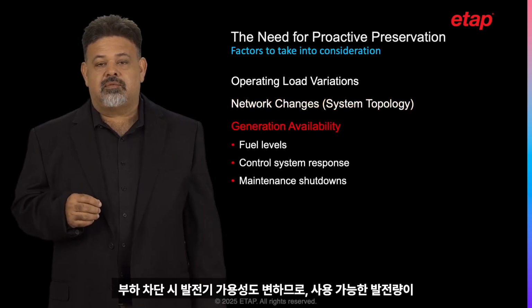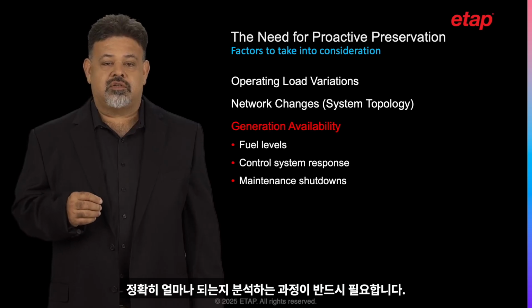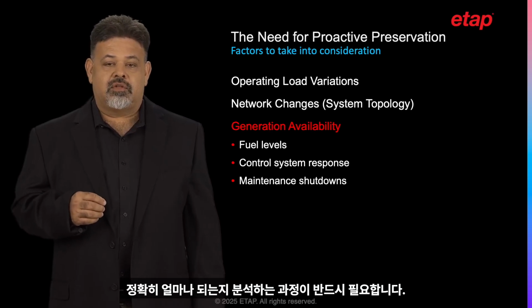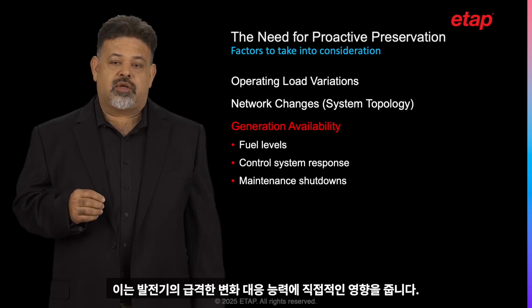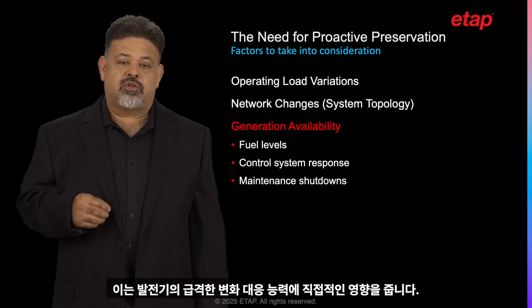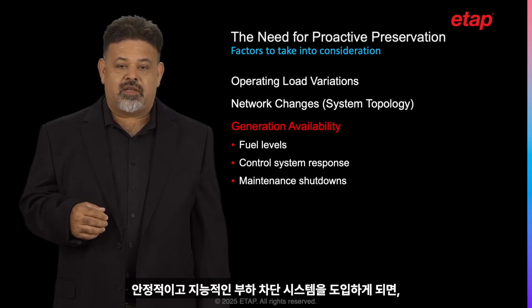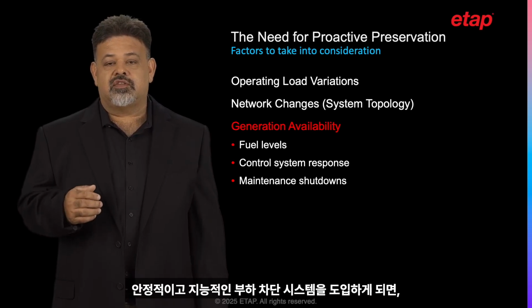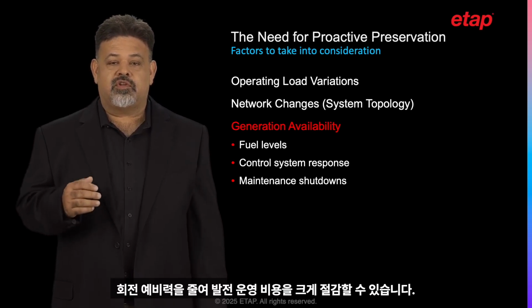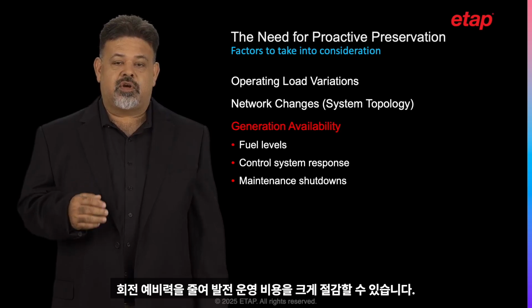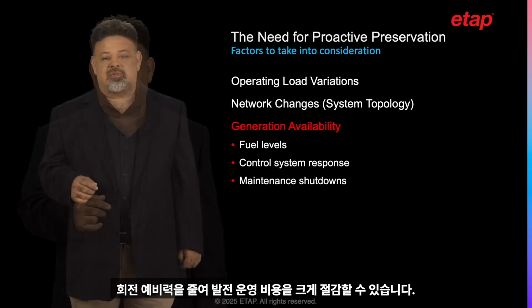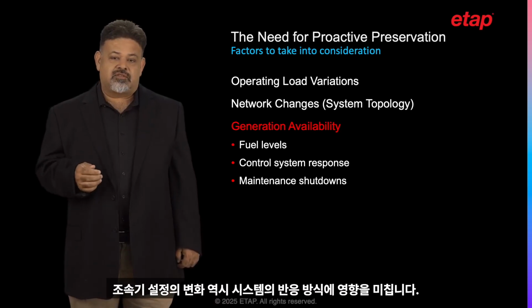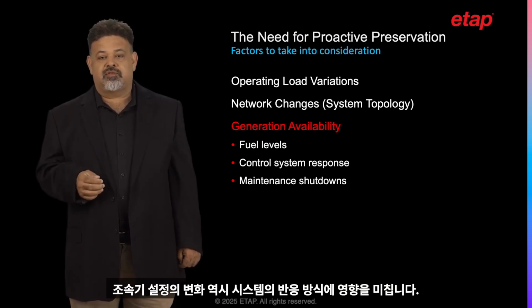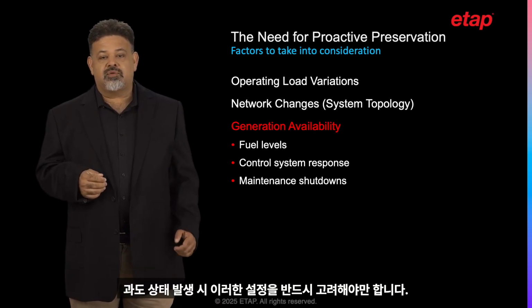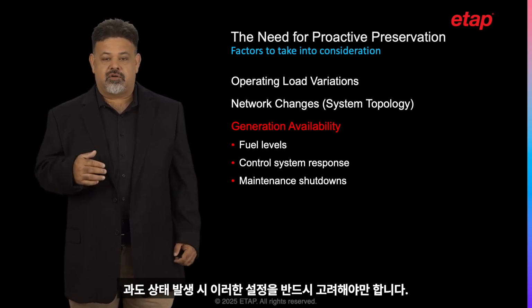Generation availability varies when performing load shedding. It is required to analyze how much generation we have available. This has a direct impact on the available generators to respond to sudden changes. A reliable and intelligent load shedding system can help you reduce such costs by reducing required spinning backup generation. Changes in your governor settings also impact the way the system responds. These settings must be taken into account when transient conditions occur.